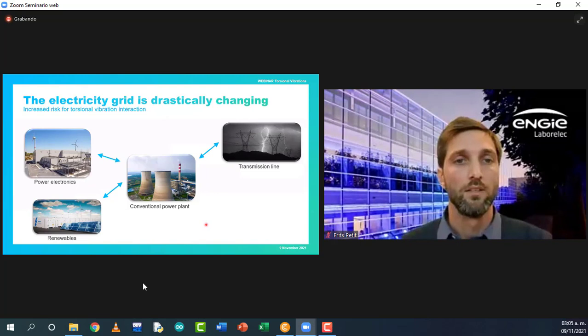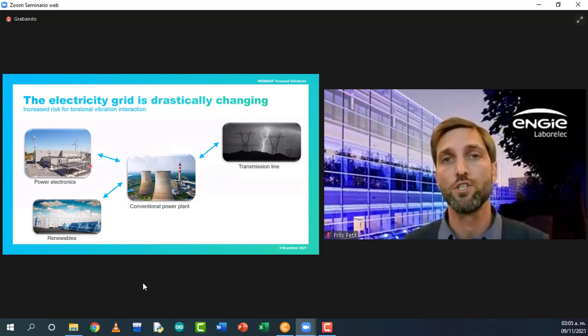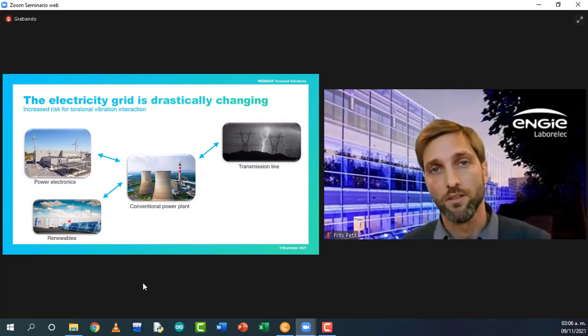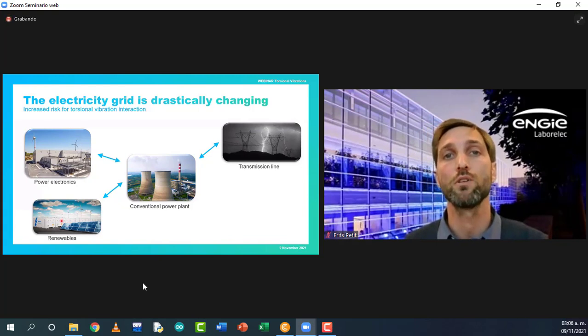That's shown here on the next slide. So we have lots of changes on the electrical side on the grid. For instance, an increasing amount of renewables. We have much more solar farms, wind farms. And what they do is that they reduce, for instance, already the inertia in the grid. They don't have the kinetic energy that your turbogenerator shaft line itself has. So this means that when running through an electrical fault, it's harder to do so with these renewables. This means that they need compensation for this reduced inertia, for instance, by adding more power electronics. In their turn, these power electronics can interact with the torsional vibrations of your shaft line.